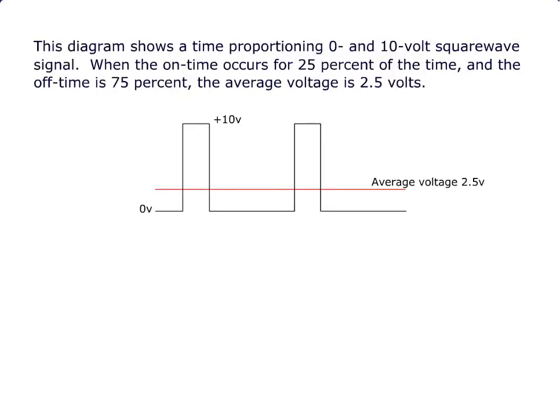This diagram shows a time proportioning 0 and 10 volt square wave signal. When the on time occurs for 25% of the time, the off time is 75%. The average voltage is 2.5 volts.